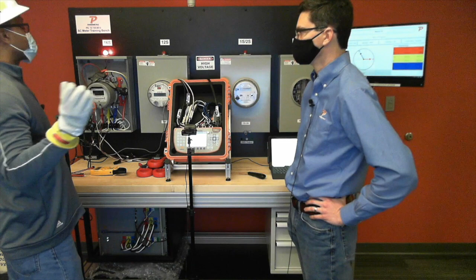All right, so let's see here. Last one. So here we go. First thing we're going to do, again, if your meter has any type of indicators on it, just take a look. All right, B phase. Okay, so it's telling me something. And then, of course, I'll check my transformers while I'm there. I'm looking at my hookup. This is saying B phase voltage, so I'm just going to make sure that my connections are good, in which they are.